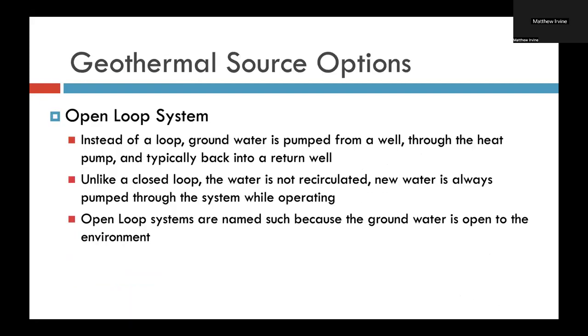So in an open loop system, instead of a loop, groundwater is pumped directly from a well through the heat exchanger of the heat pump, and then typically back into a return well. Unlike a closed loop, the water is not recirculated, and new water is always pumped through the system while operating. Open loop systems are named such because the groundwater that you're pumping through the system is open to the environment. Next.